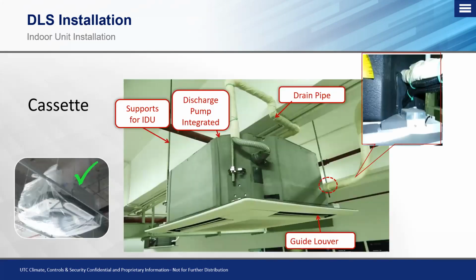Now inside of the cassette unit itself, you'll see we have two main connections up there. We have the point of condensate management, or condensate removal, which you'll see there with a little flexible drain line. This unit has a built-in condensate lift pump to lift the water either to a secondary pump or a natural drain. And then of course we have our refrigeration line set connections, which will be accessed if we have a leak issue or on the initial startup.